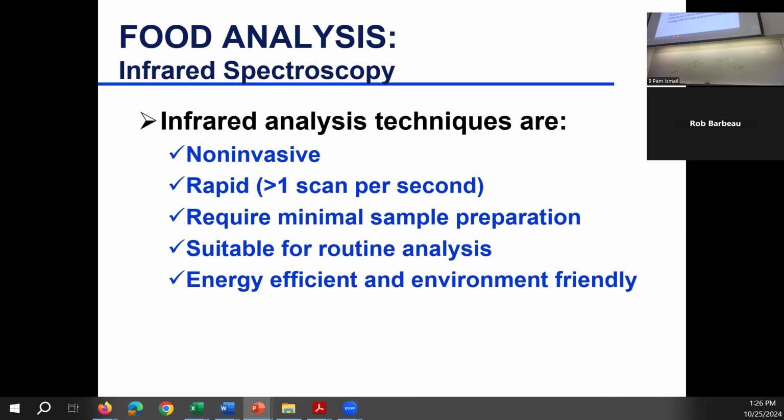So for the IR, you need to tell it, you will run standards and you say, this sample has 5% fat. This sample has 10% fat. This sample is 12, and so on. And then you do the calibration. How do you know what to use to determine the sample fat?